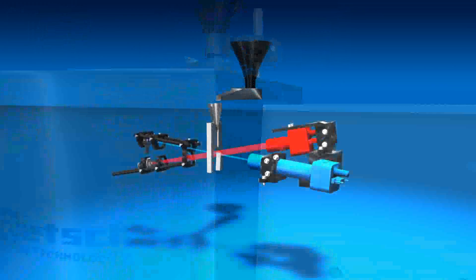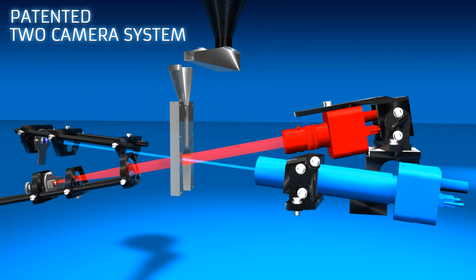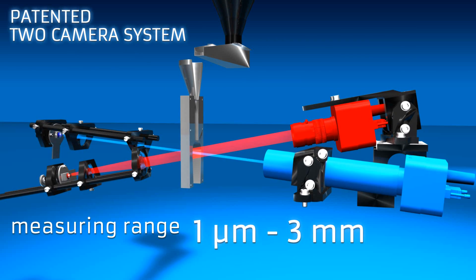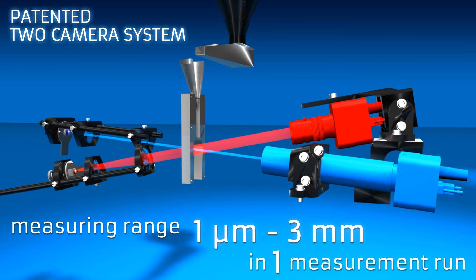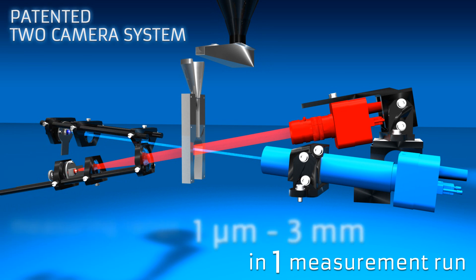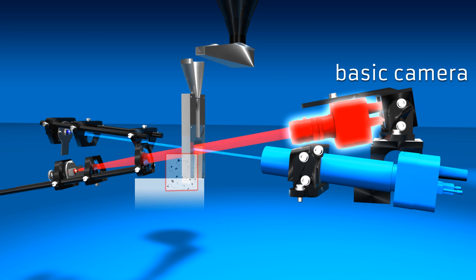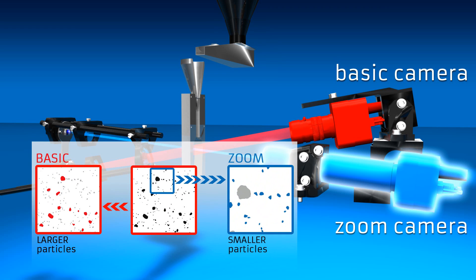Thanks to the patented two-camera system, the CamSizer XT covers an extremely wide measuring range from 1 micron to 3 millimeters in one measurement run. A basic camera detects larger particles, whereas a specially designed high-resolution camera analyzes small particles accurately.